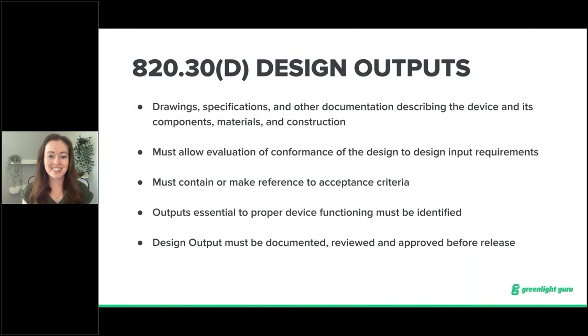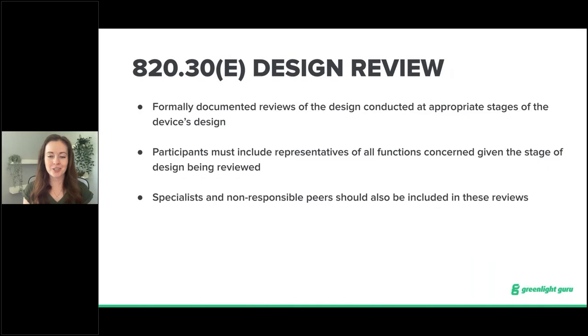Now we're going to deep dive into what design reviews look like. The definition from Part 820 is a documented, comprehensive, systematic examination of a design to evaluate the adequacy of the design requirements, evaluate the capability of the design to meet these requirements, and to identify problems. Formal design reviews are intended to help provide a systematic assessment of design results, including the device design and associated designs for production and support processes.